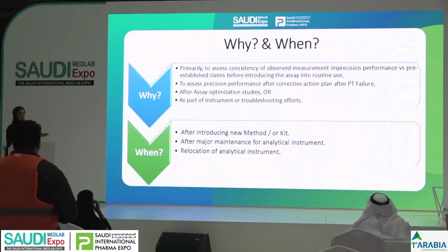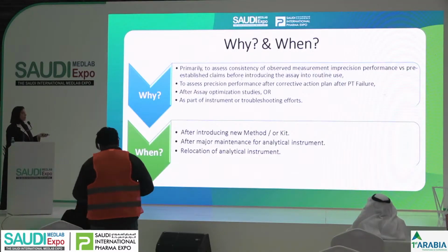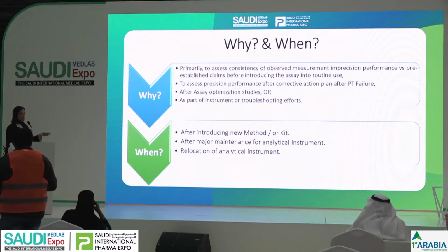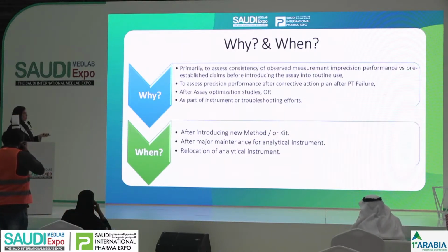As part of instrument troubleshooting efforts, if I have a problem with my instrument, I have to verify my precision after fixing it as well. Always after introducing a new test, methodology or kit, after major maintenance, changing major parts in the analyzer, or relocation of the instrument.